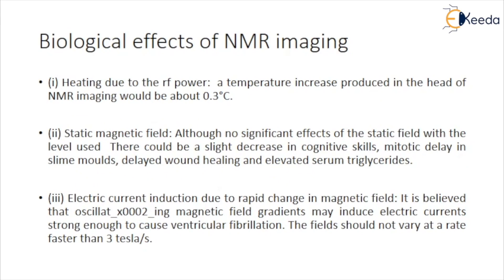Biological effects of NMR imaging: heating due to the RF power — the temperature increase produced in the head from NMR imaging would be about 0.3 degrees Celsius, which does not seem likely to pose a problem. Regarding the static magnetic field, although no significant effects at the levels used in NMR are confirmed, possible side effects of electromagnetic fields include a slight decrease in cognitive skills, mitotic delay in slime moulds, delayed wound healing, and elevated serum triglycerides.